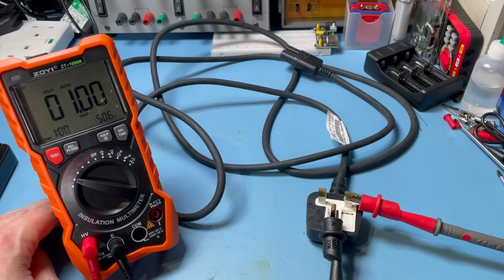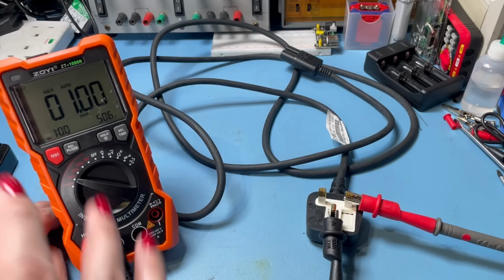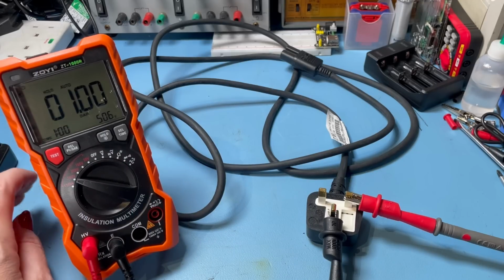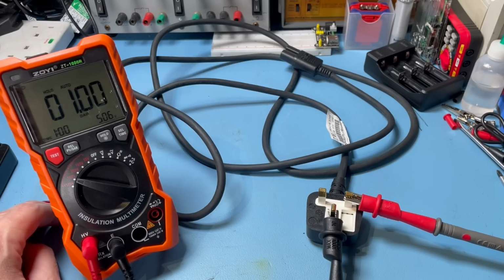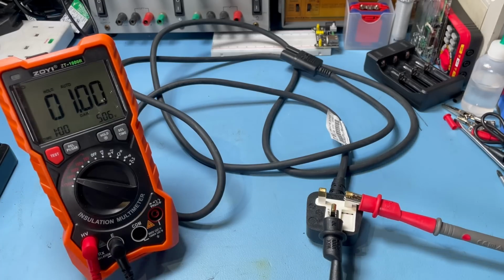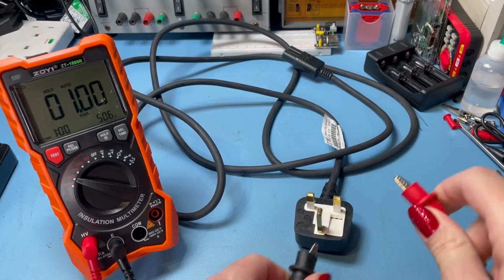So if you've got a lot of stuff to test, you're better off doing DAR tests first, and then if you see anything that looks a bit sus, then do the PI test, which takes longer and will give you an indication of how good that insulation is over a longer period of time. Is it going to break down under heat or stress or anything like that? This one is reading 1.00.